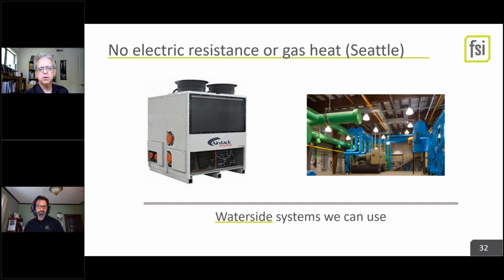So when you're in a mode where you're just heating, then this chiller is just going to have to dump that chilled air, waste it out to the outside. Is that right? It usually does. There are some fancy things we can do, and we have things like data servers where we actually run 2 pipes into a chiller, and we cool one side and we heat the other side, and it's great. It's so efficient. However, most buildings don't have some huge data center hanging out, giving them all the free heat they want. So usually, just like a heat pump, we're pulling in air from outside and we're rejecting colder air back out to pull the heat out of it to push it into the building. So that is a reality. And then of course that flips in the summer. You pull in air and you push it out hotter because you rejected heat to it.